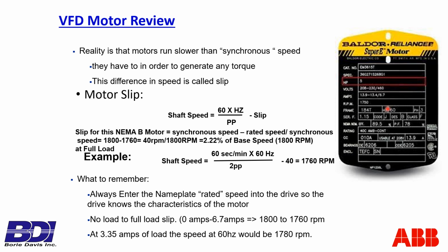Rarely do they, because people don't design things to run fully loaded. But the fact is, the motor's fine. And if it's fine when it never even operates at its own nameplate, then surely you can realize it'll be fine at all these other speeds too, based on the satisfied torque equations we've worked with, and the fact that this nameplate is just telling you one exact point that this motor's designed for.